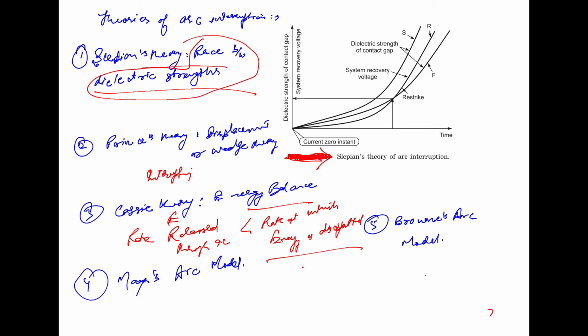Cassie developed his equation for the conductivity of the arc based on the assumption that the arc is governed mainly by the convection losses during the high current time interval. So Cassie's model proved to be very useful, especially in modeling the high current part of the arcing time. However, near the current zero, it is accurate only for high rates of current density.